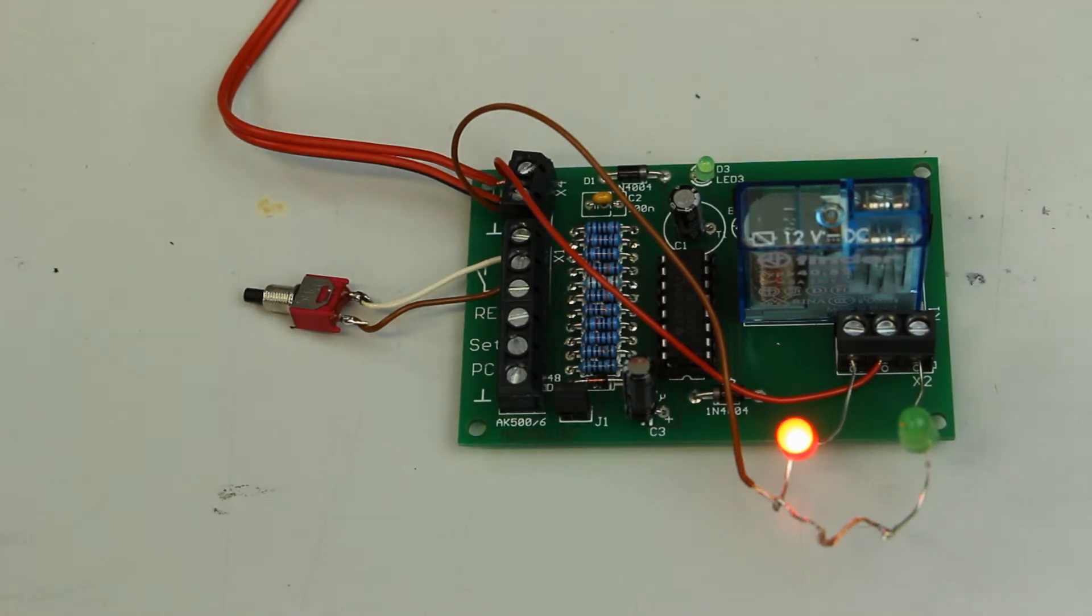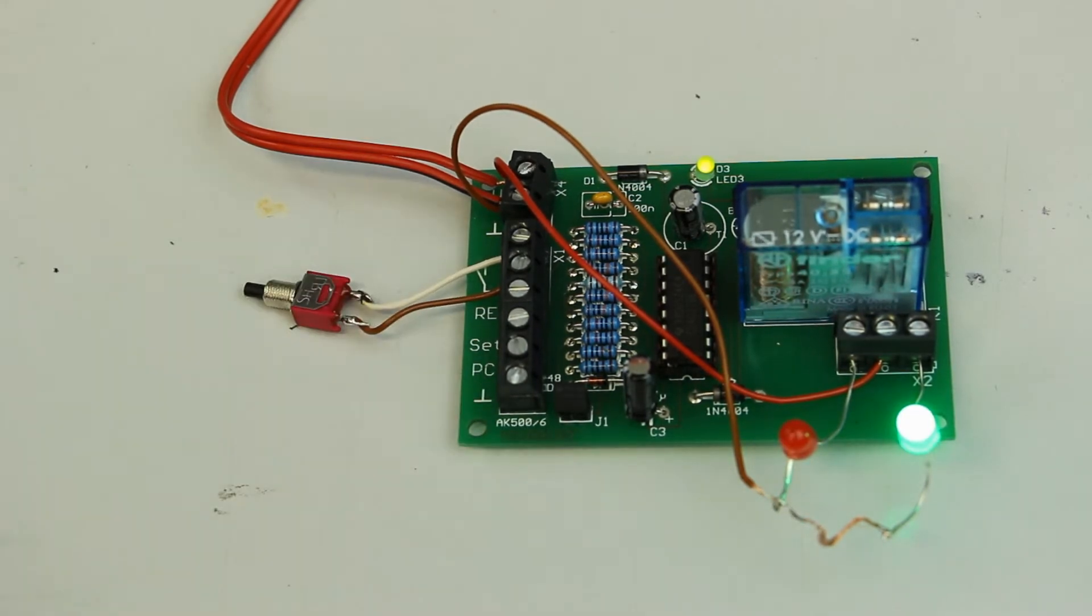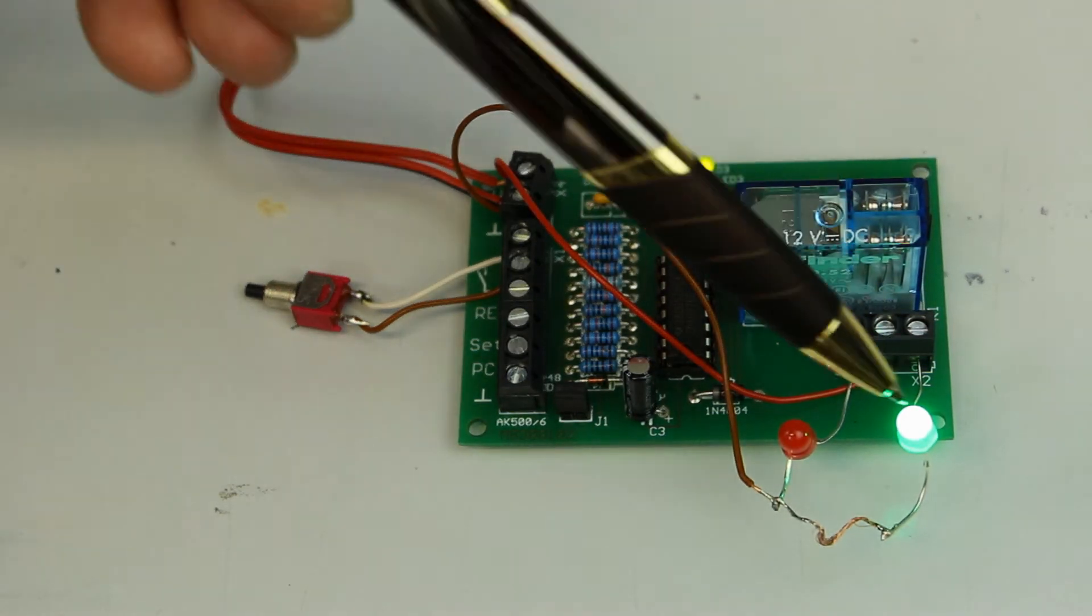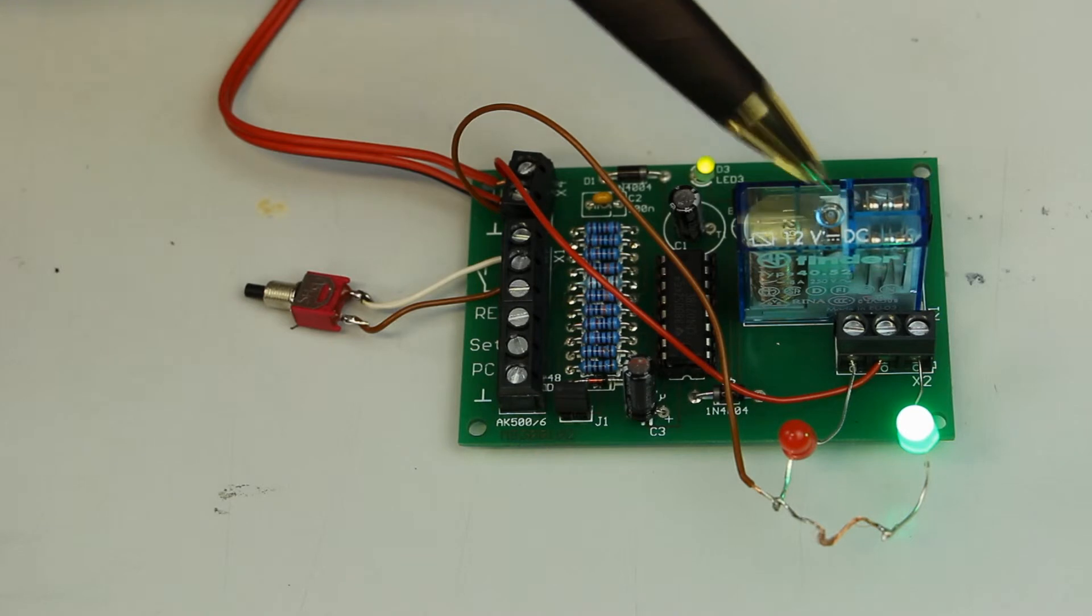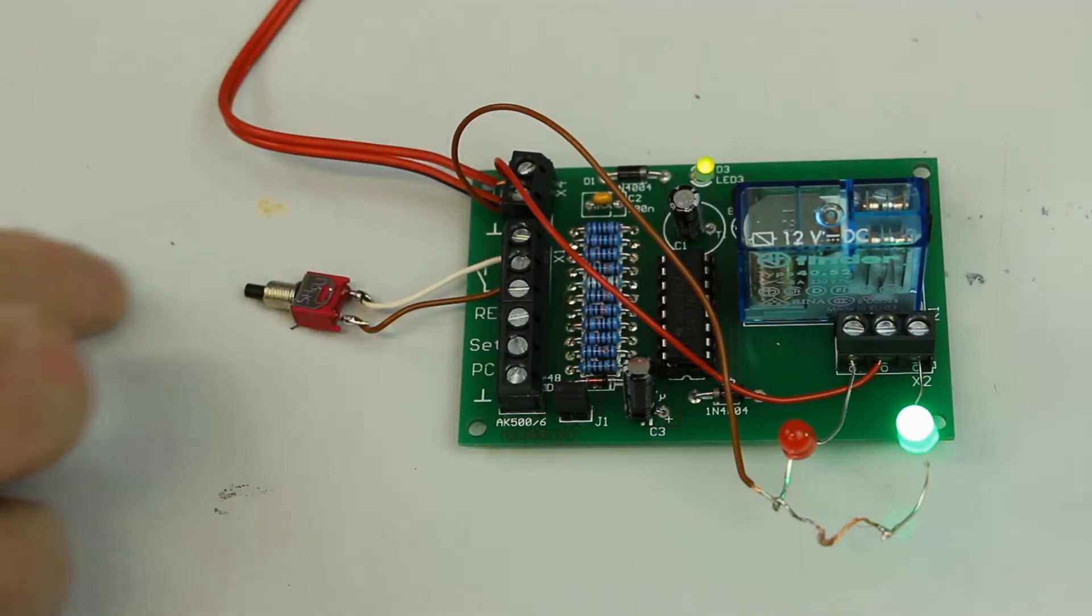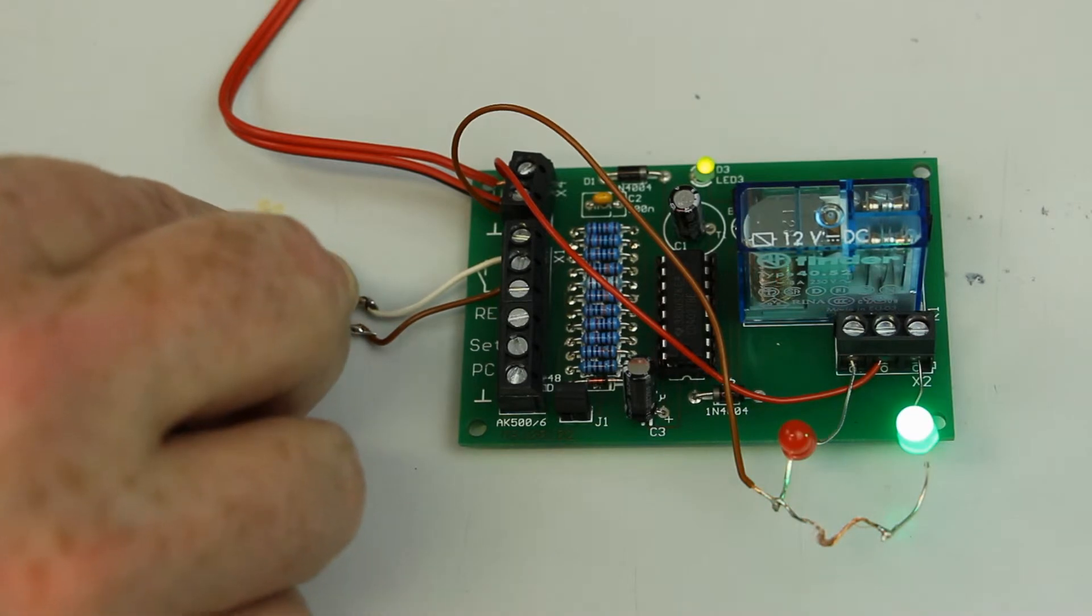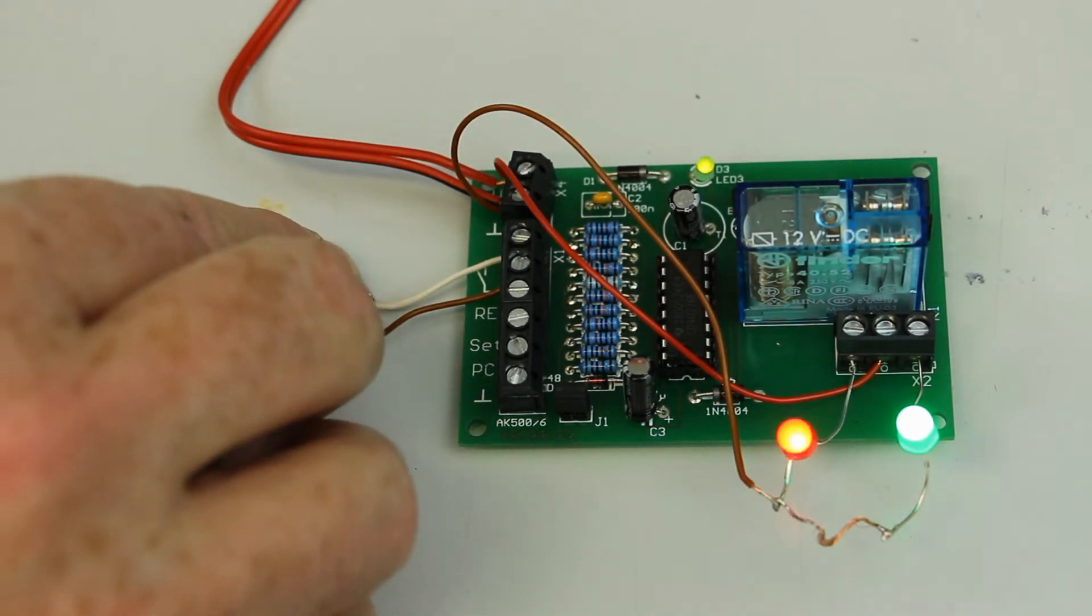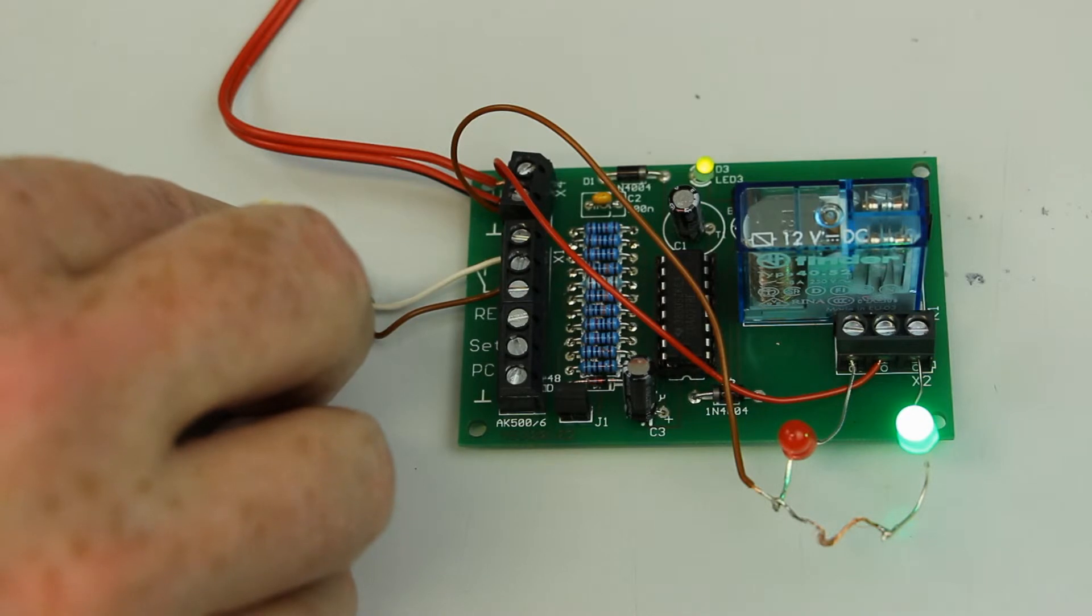Now let's take a look at what happens when we activate the push button for the toggle function, and you see it switches over to the on state, which can be seen also by this control LED, which always shows us when the relay is energized, and in parallel now we can see that both green LEDs are of course turned on. And you might have noticed there's no bouncing around because we have an anti-bounce circuit built in, so that the state doesn't bounce over between on and off depending on the quality of your push button, but it always goes only once to the other state.